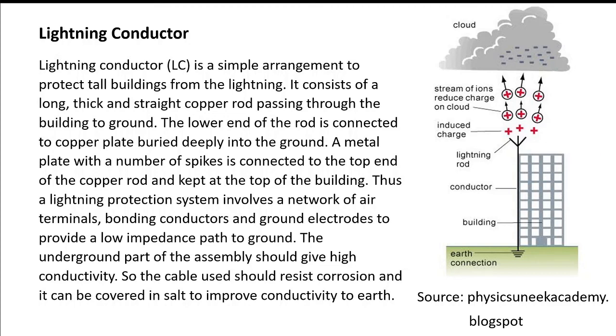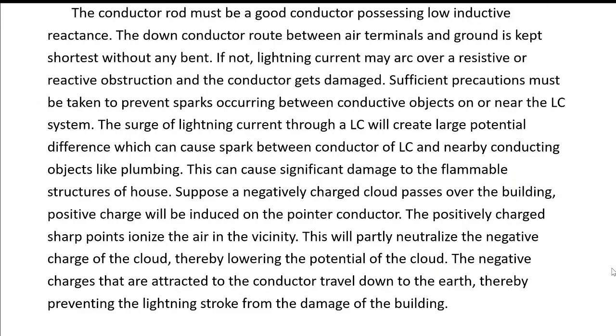Thus, a lightning protection system involves a network of air terminals, bonding conductors, and ground electrodes to provide a low impedance path to ground. The underground part of the assembly should give high conductivity. So the cable used should resist corrosion and it can be covered in salt to improve conductivity to earth. The conductor rod must be a good conductor possessing low inductive reactance. The down conductor route between air terminals and ground is kept shortest without any bend. If not, lightning current may arc over a resistive or reactive obstruction and the conductor gets damaged.